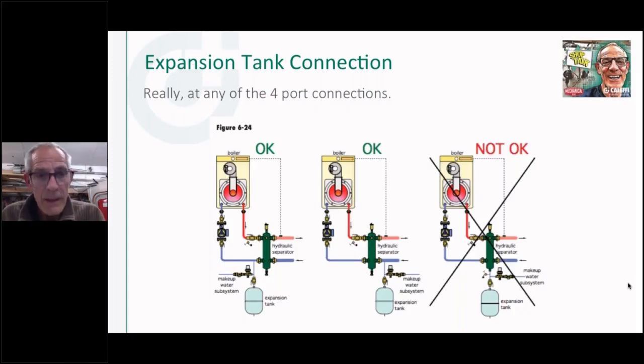Exactly. And that's why I think people misunderstand that, and they think the expansion tank always has to hang below the air purger. It doesn't. I always want my air purger, let me just show you here, at the hottest point in the system, because if this water's coming out here at, let's say, 180 degrees, that's where I'm going to get my best air removal. So I want my air purger in this position, but I don't necessarily need my expansion tank, as you can see in this condition here, hanging off the bottom of the air purger, or air separator, whatever you're using. And I think people misunderstand that relationship, that everything has to be grouped together. When you put an expansion tank, I've got to have my air purger.